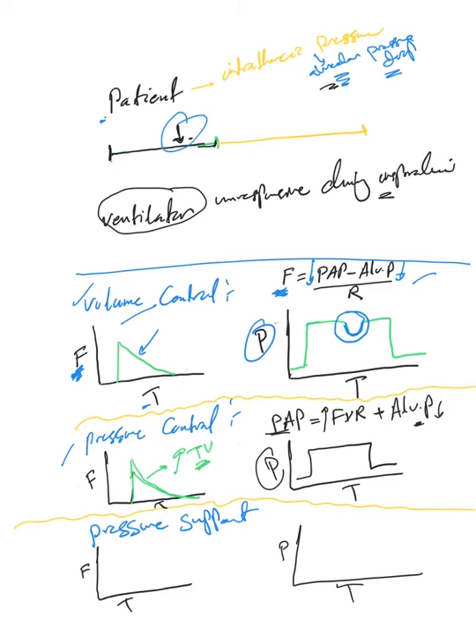In pressure support, it's again a pressure target, so the same thing will happen. The flow will increase to compensate for the drop in pressure, as explained in pressure targets.